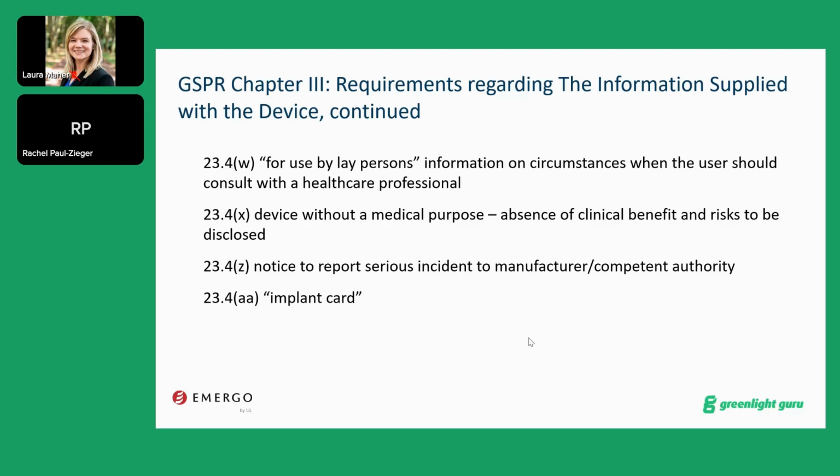You have a requirement for a notice that a serious incident must be reported to the manufacturer and competent authority. So this is a new requirement. And you have the requirement for an implant card if applicable for your device.